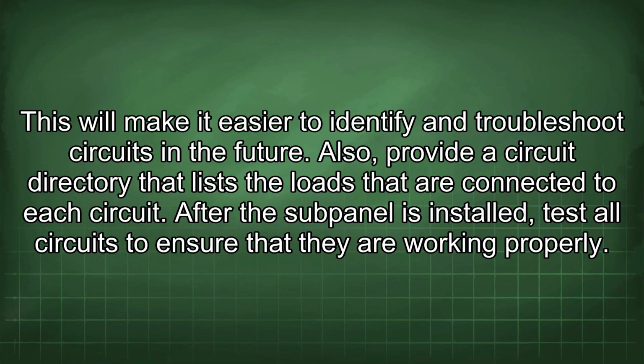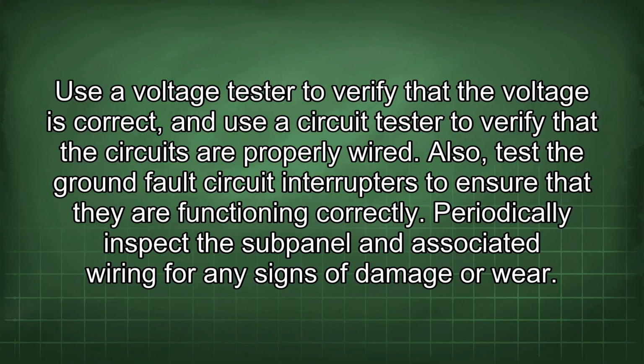After the subpanel is installed, test all circuits to ensure that they are working properly. Use a voltage tester to verify that the voltage is correct, and use a circuit tester to verify that the circuits are properly wired. Also, test the ground fault circuit interrupters to ensure that they are functioning correctly.